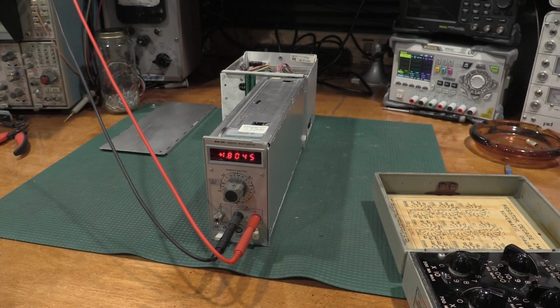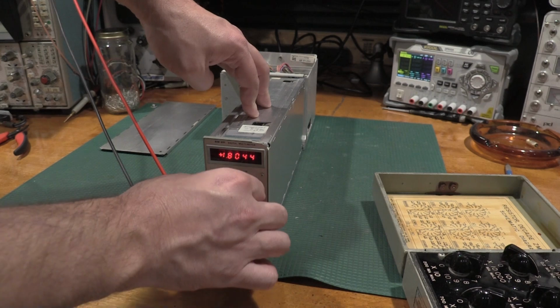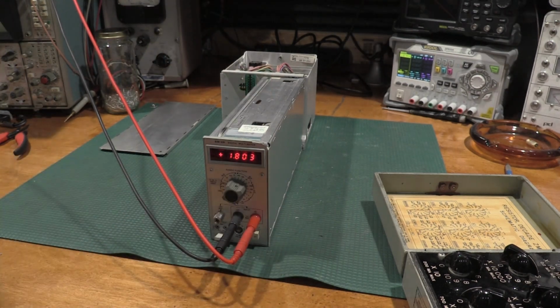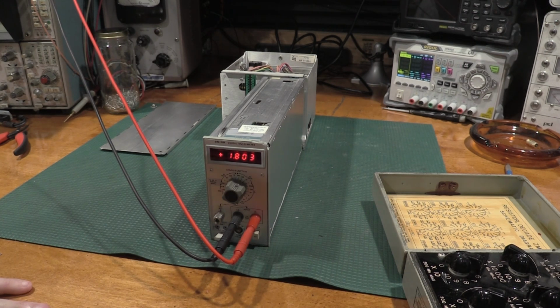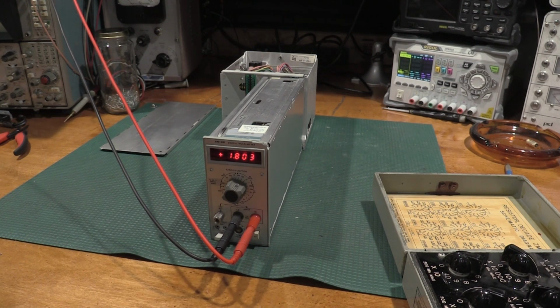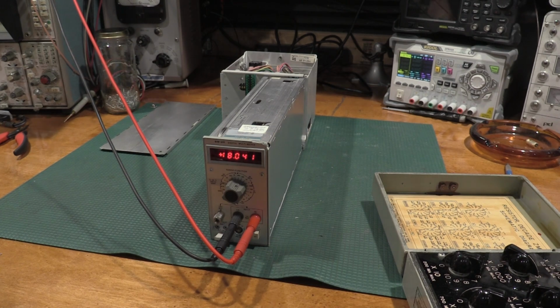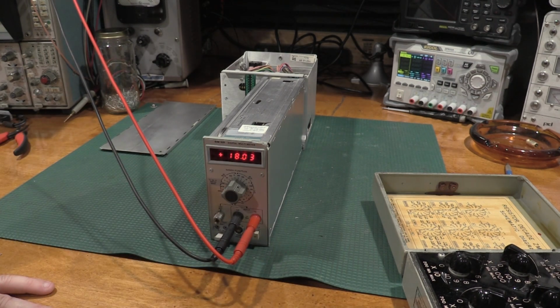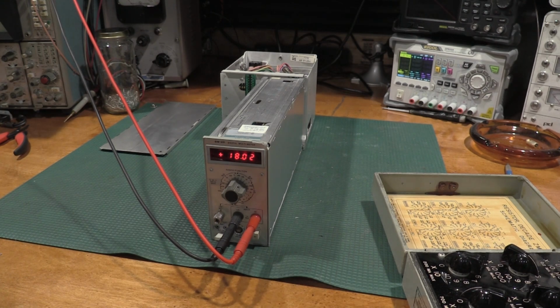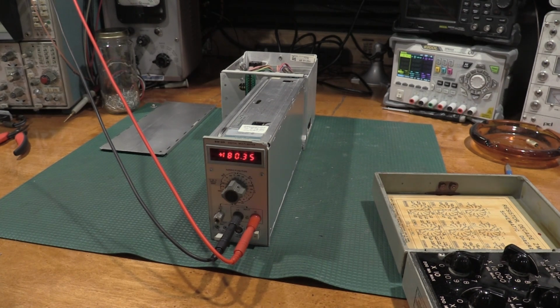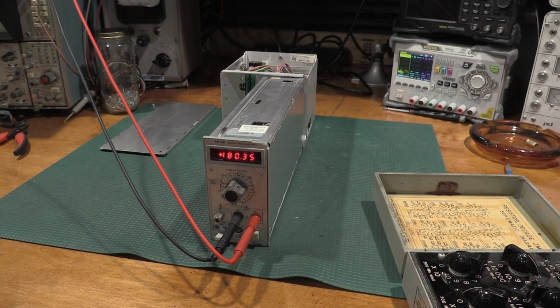And it's just checking the validation at this point of the current sense. So we'll bump it up. That is the 20 milliamp range, so we'll go to 18 milliamps. Looks good. We'll probably go to 180 milliamps. Oh, 180 milliamp, not amp. Don't do that. So we have switched ranges now. We're at 250 millivolts burden voltage. Let's kick it up one more.